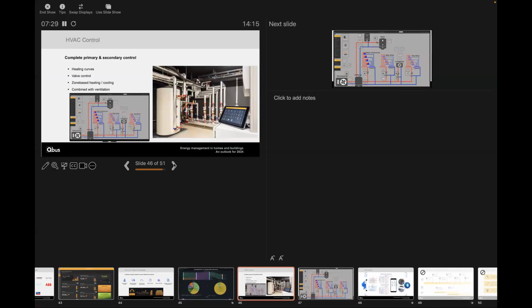In continental Europe we have both air conditioning in summer and heating, issues you may not have here. In lots of older buildings, they have two systems, cooling and heating, with separate thermostats fighting each other. We've seen installations literally throwing money through the windows - when heating came up, cooling started to cool down, and heating moved up again. It was ridiculous. Here you don't have heating, but maybe in the mountains you might.